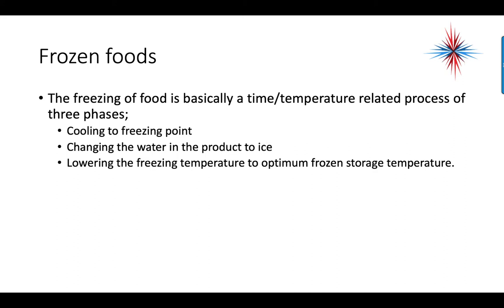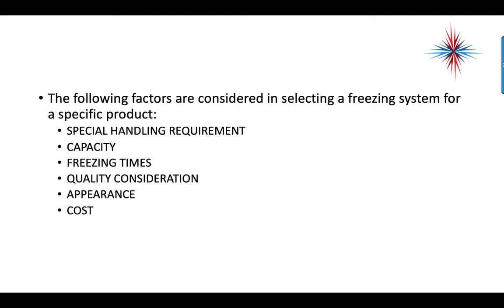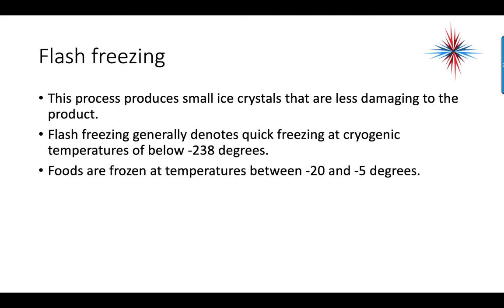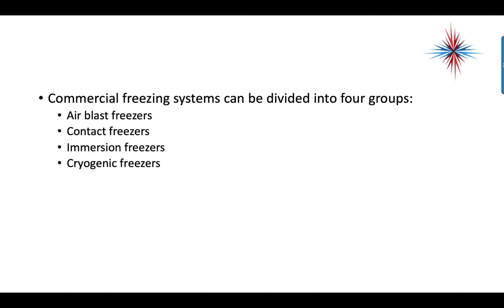Freezing of food is basically a time-temperature related process of three phases: cool it to the freezing point, change the water in the product to ice, and then lower the temperature to optimum frozen storage temperatures. Factors considered in selecting a freezing system include special handling requirements, how much you're freezing, how fast you want it frozen, quality considerations, appearance of the product, and cost. Flash freezing is a process that produces small ice crystals that are less damaging to the product — generally a quick freezing at cryogenic temperatures below negative 238 degrees. Foods are typically frozen at temperatures between negative 20 and negative 5 degrees. Commercial freezing systems can be divided into four groups: air blast freezers, contact freezers, immersion freezers, and cryogenic freezers.